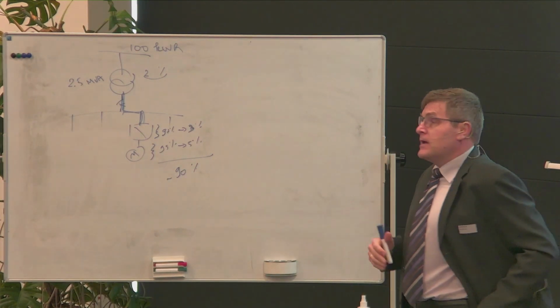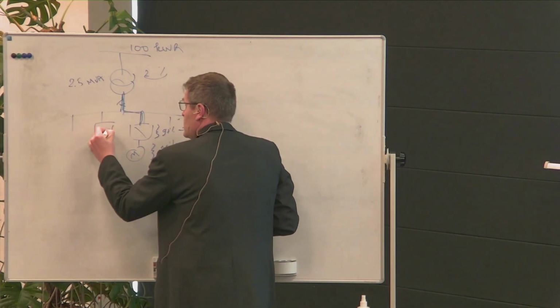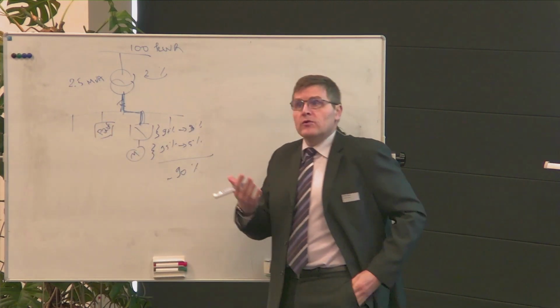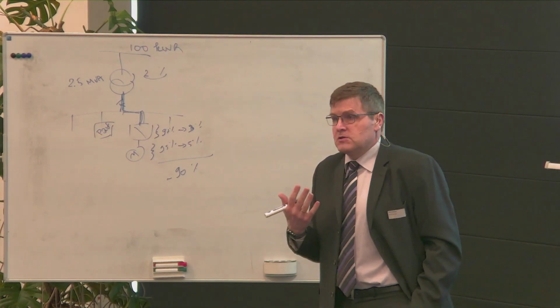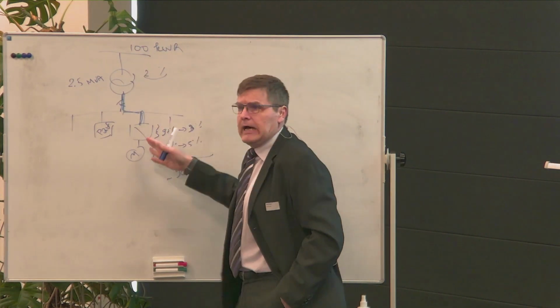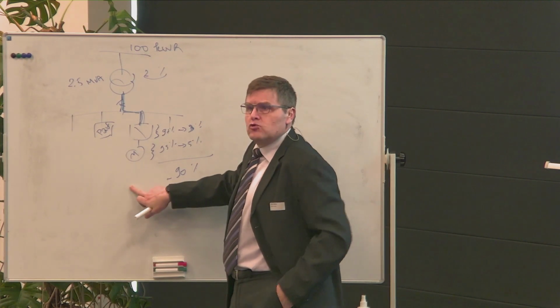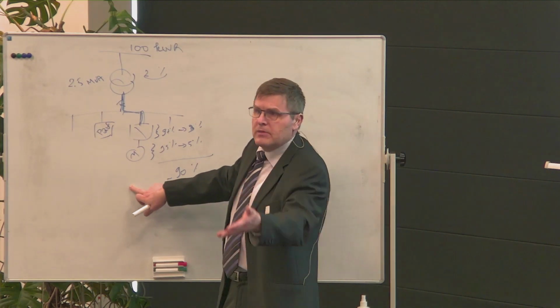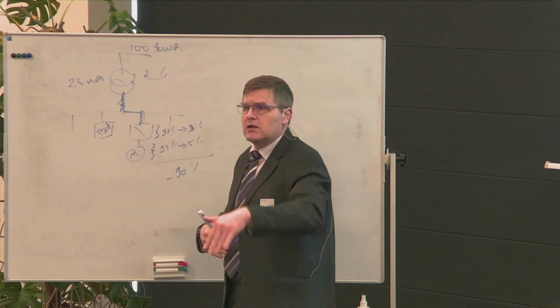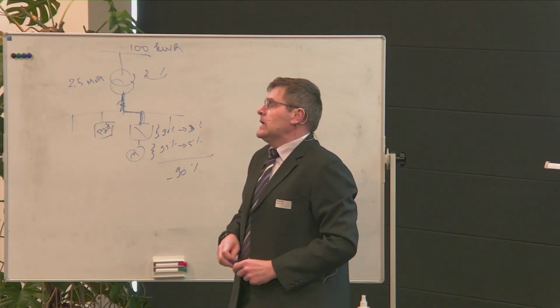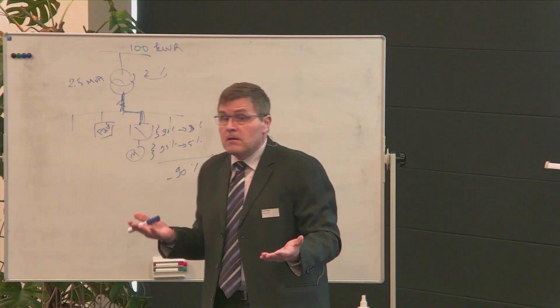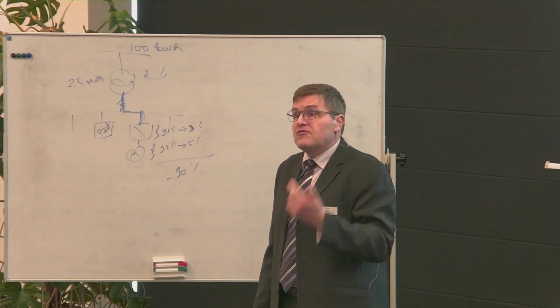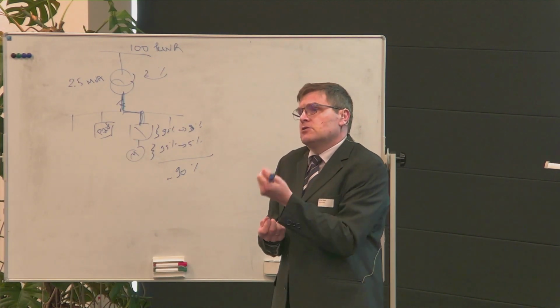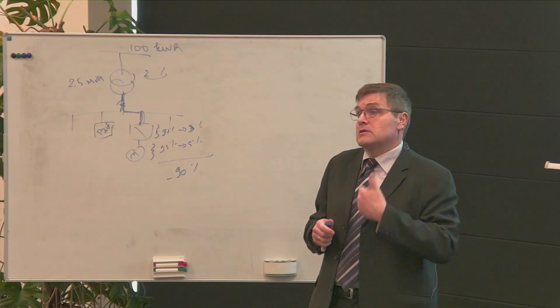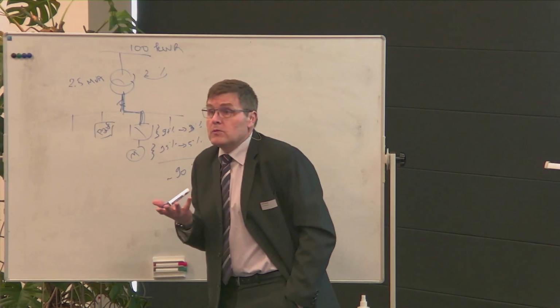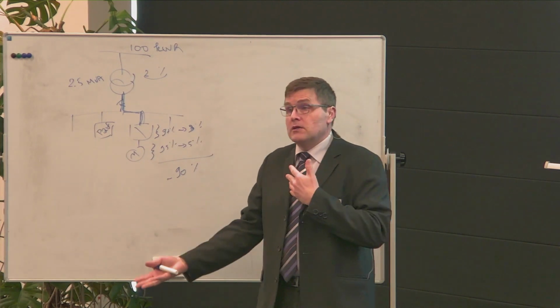The active filter here, we were assuming a power quality filter or active harmonic filter. And we agreed with the customer to have a measurement of the efficiency. So it is the total energy consumption of this line compared to the tons of pasta produced, because from one month to another, you produce 100 tons of pasta, the other month 90 tons. So we used a ratio, energy divided by tons, so we have the energy per ton. After one month, we saw about 0.5% energy savings, but it was not relevant because the accuracy of the measurement was about 1%, so we could not say that it is an energy saving, because the active filter also consumes some energy. There are some losses inside, so the gain counterbalances the losses.